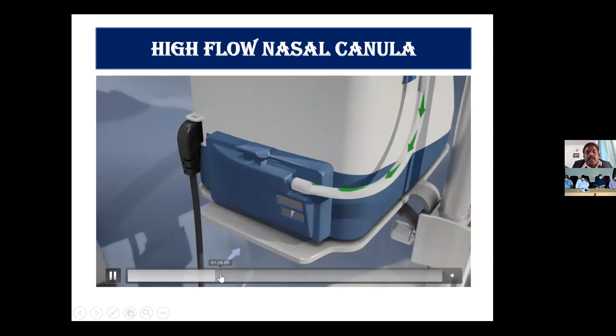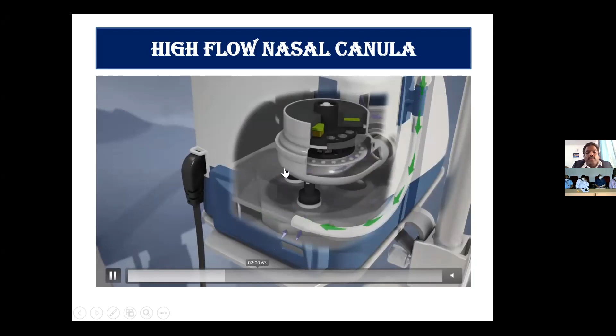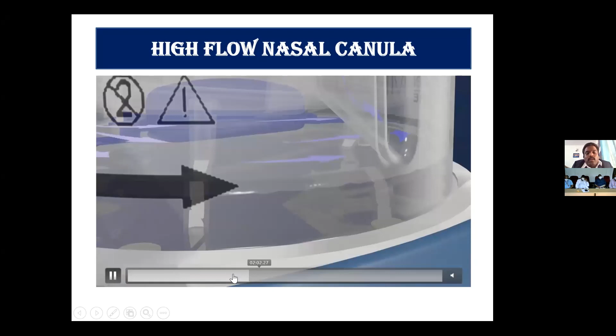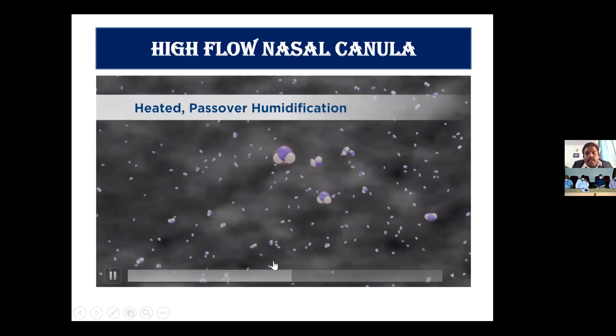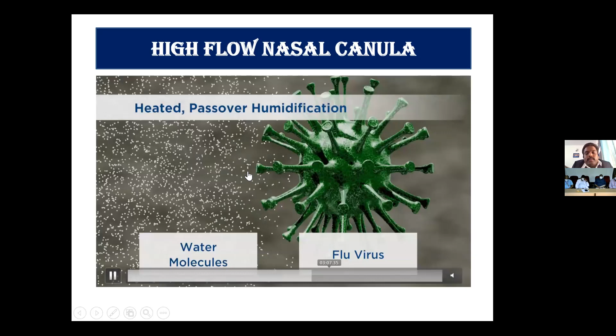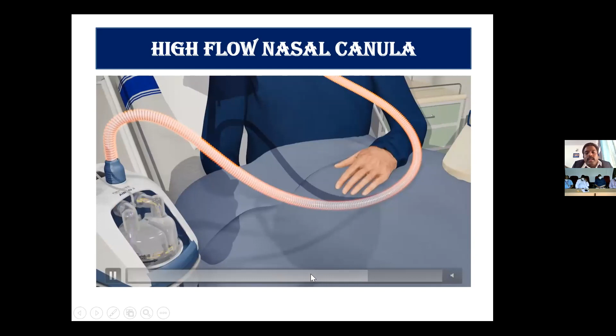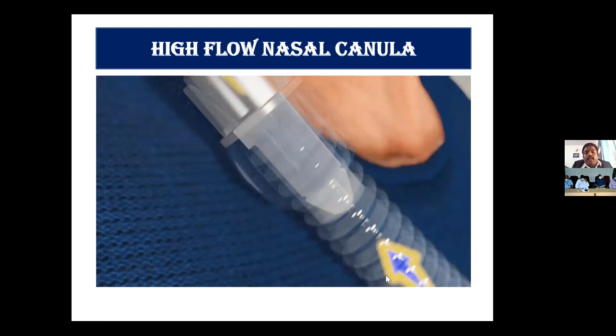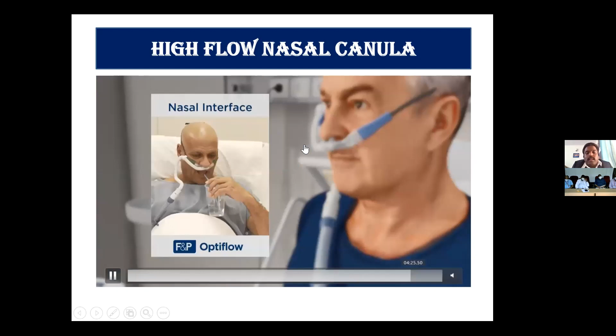This is the air oxygen blender which is inside, so that it gets collected in the humidifier process, that is the thermal sensing unit, where the gas is humidified, heated, and then passes over the tubing. You see, these are heated insulated tubings through which the oxygen is given. This is the port which sends the gas, thermally sensitive, to prevent any after effects of inadequate humidification in the nasal passage. You have the nasal prongs here, which will be very useful when the patient is active but having hypoxia, as in happy hypoxia in COVID-19.